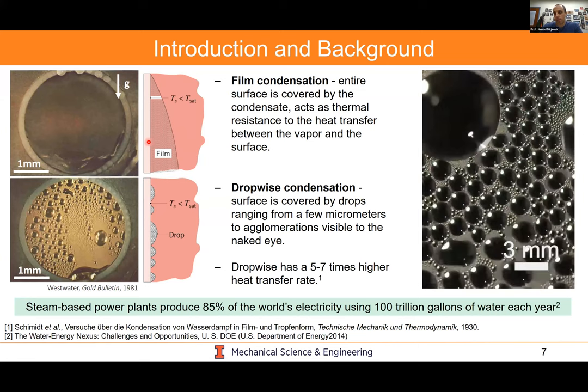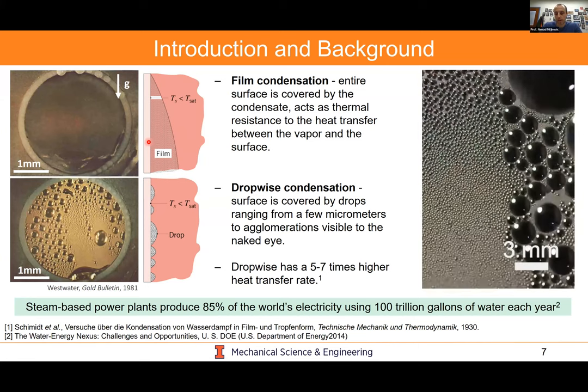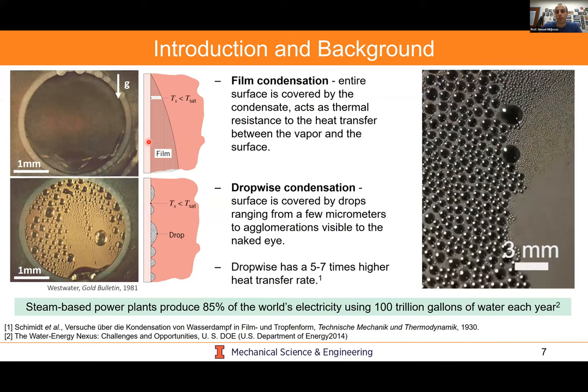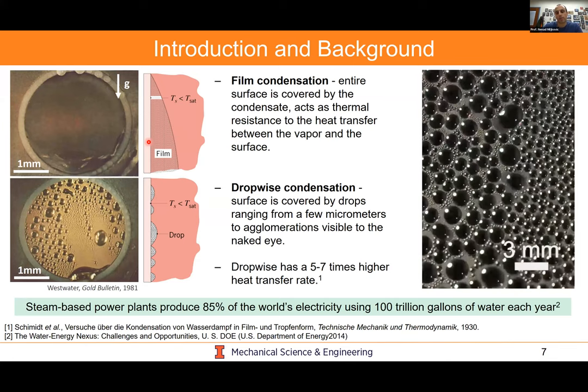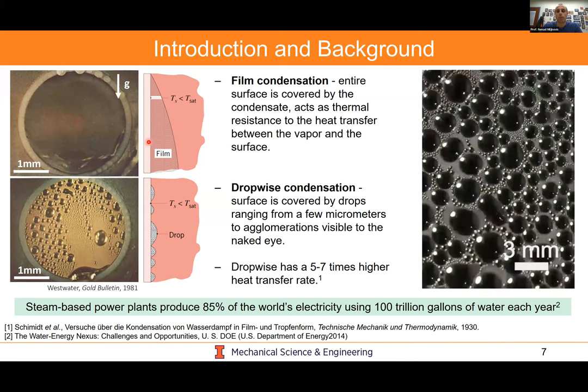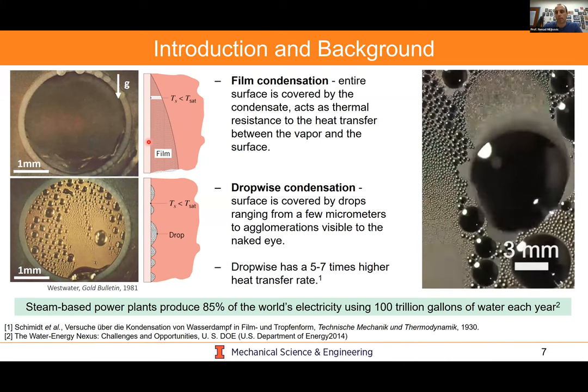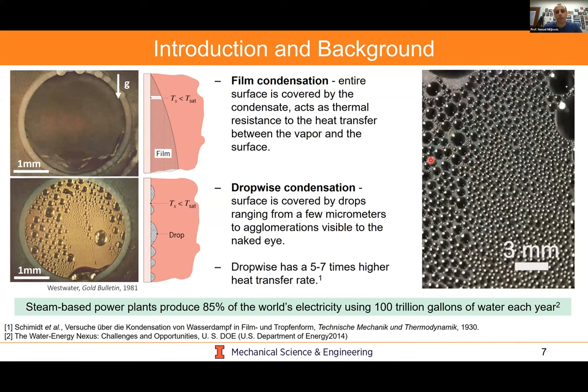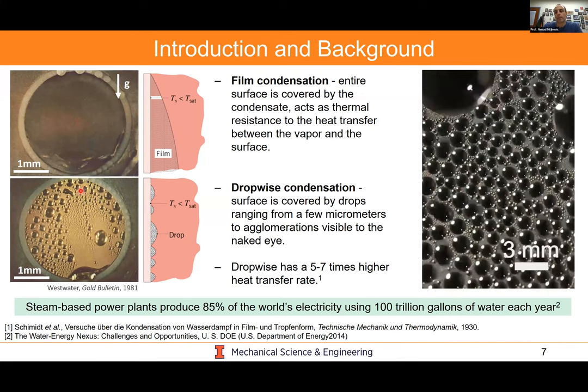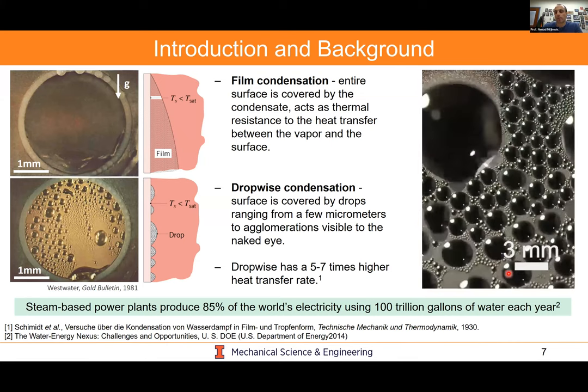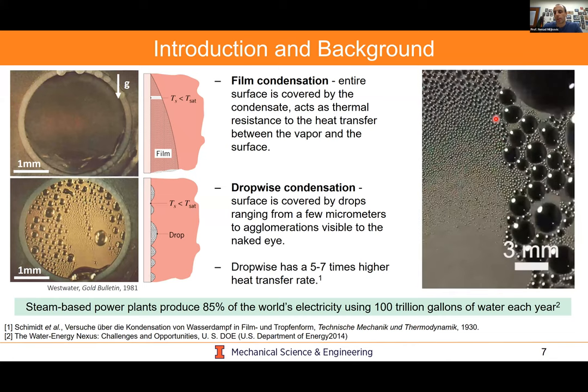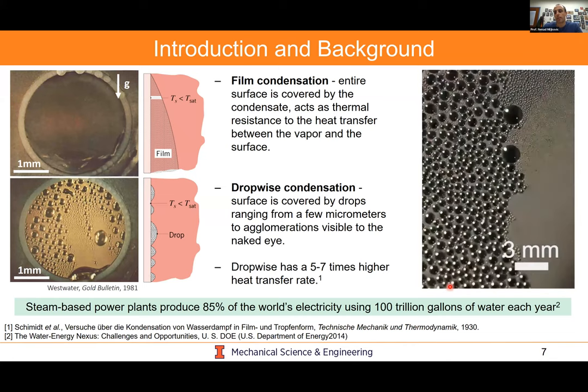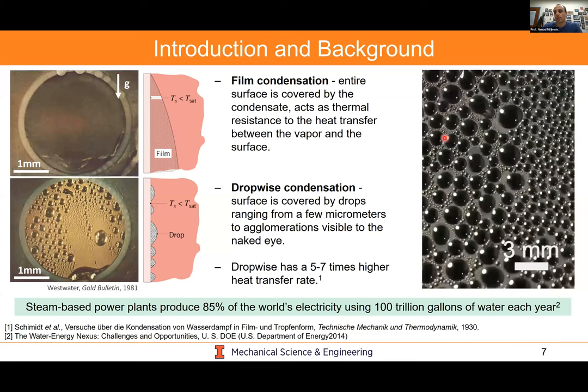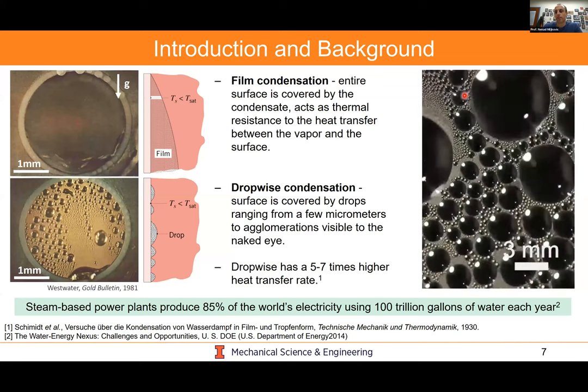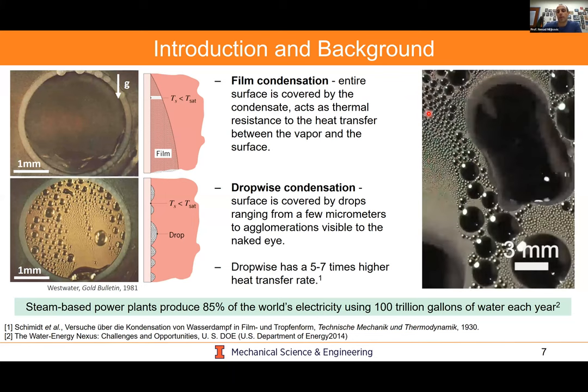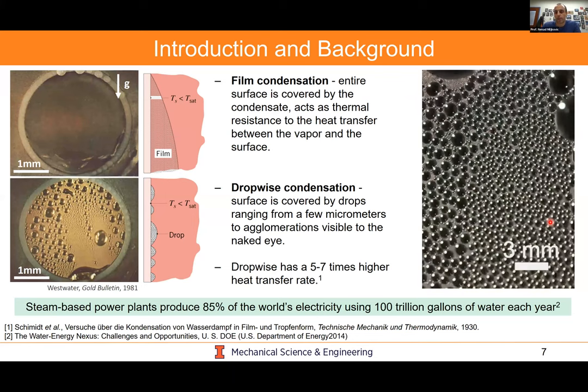Well over 80 to 90 years ago, a gentleman in Germany named Schmidt discovered that if you take one of these tubes and spread animal fat on the outside, you get something called dropwise condensation. You see this in the video on the right and in the bottom left image, where distinct droplets form on the surface, coalesce, grow, and eventually shed from the surface. It's this dropwise condensation process—this renucleation, this clearing of the surface—which makes this heat transfer phenomenon 10 times more efficient than film-wise condensation.